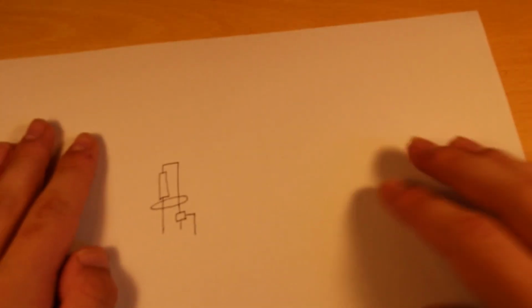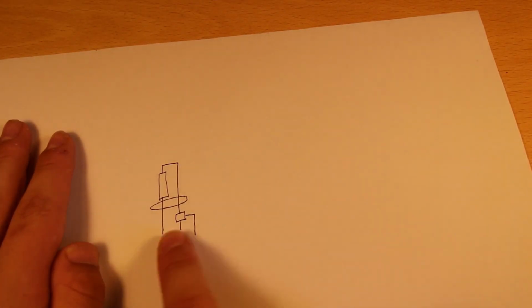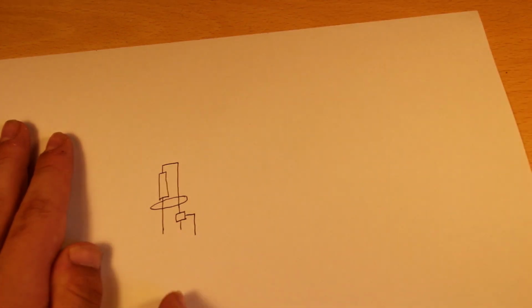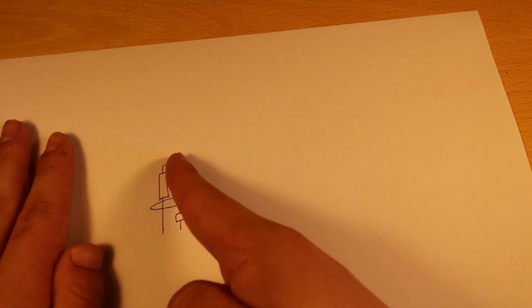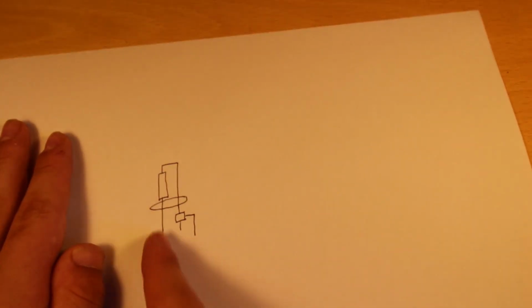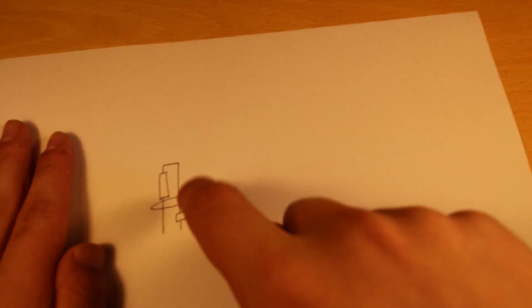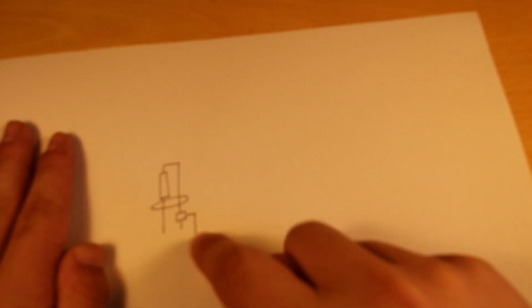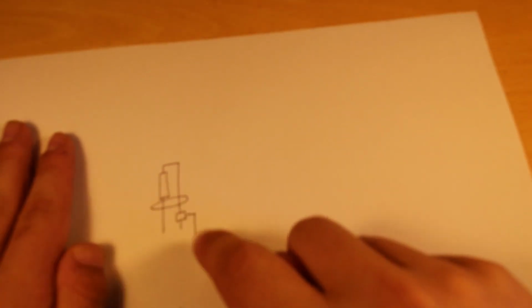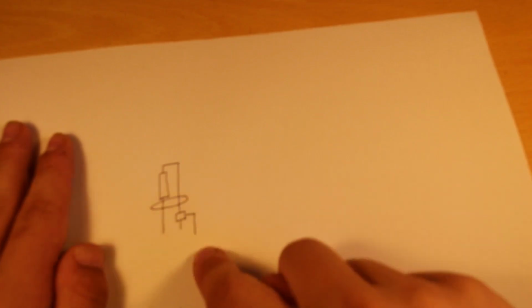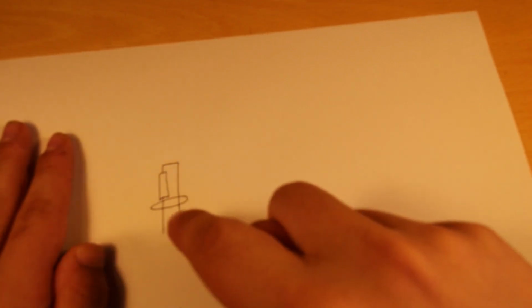So, here we have a circuit with the live, the PEN, the earth, and a load resistor. This here is where your RCD will go. Your RCD only cares about whether the current going up here is the same as the current coming down here. So the current comes up the phase, goes through the load, back down the neutral, the RCD sees no imbalance, then it diverts here and goes down to earth. That is why the RCD will not see the imbalance, because the leakage to earth happens after the RCD is checking. If it happened here, the RCD would trip, but not here.